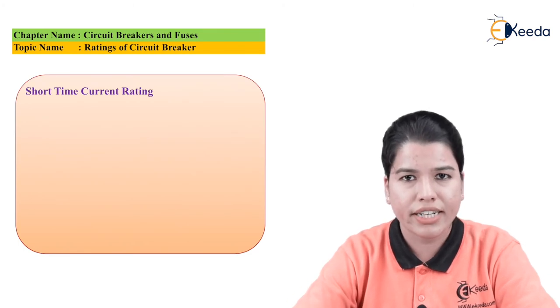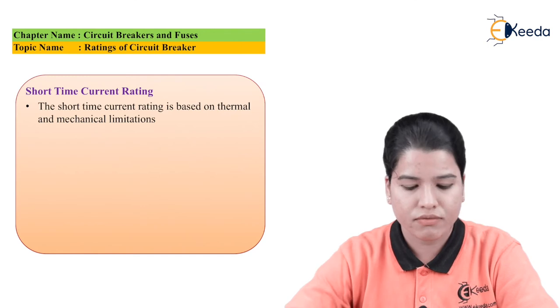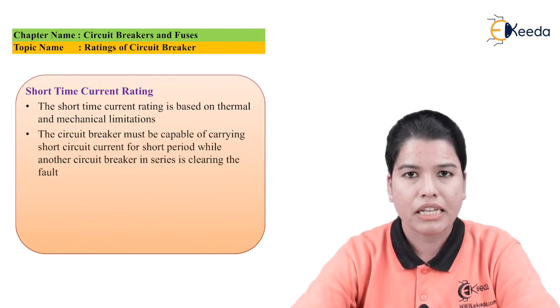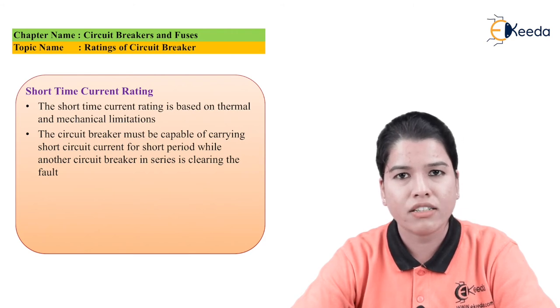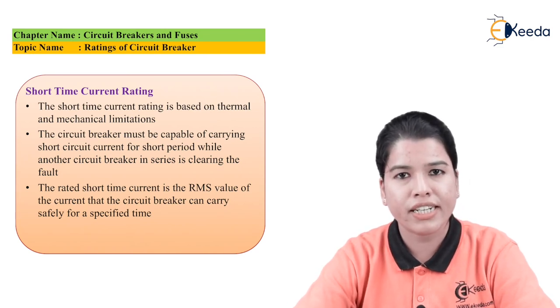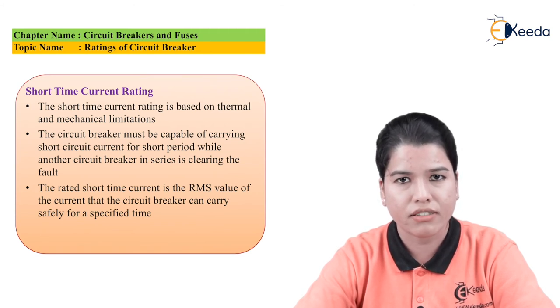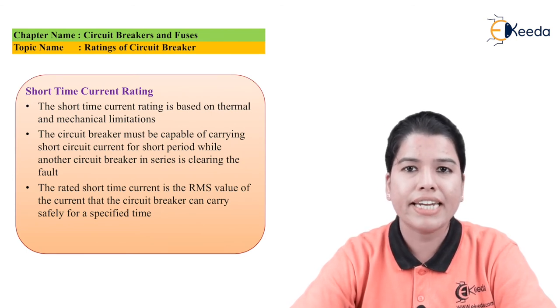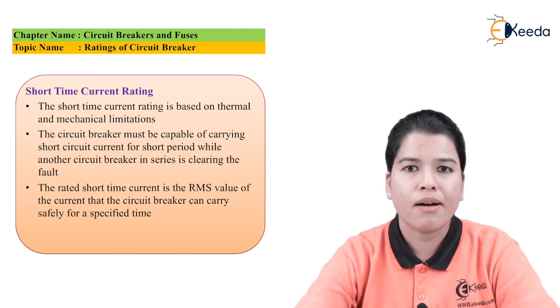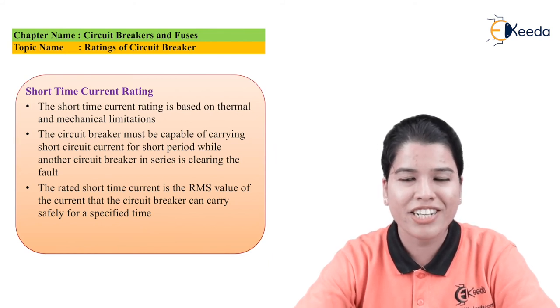Next is short time current rating, which is based on thermal and mechanical limitations. A circuit breaker should be capable of carrying the short circuit current for a very small time when another circuit breaker connected in series is clearing the fault. The rated short circuit current is the RMS value of the fault current that the circuit breaker can carry safely for a certain period of time. These are the various ratings of the circuit breaker that are all taken into consideration while designing it, and a particular circuit breaker is selected for a particular application depending upon these ratings.